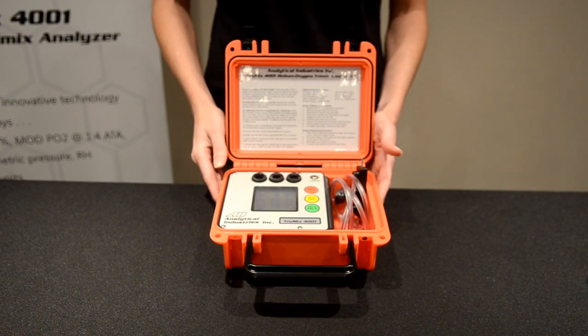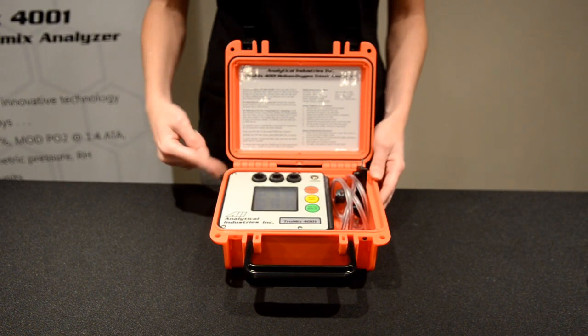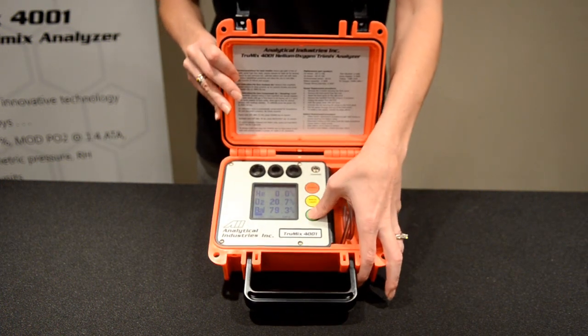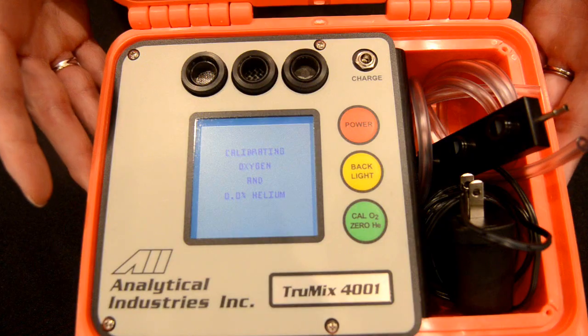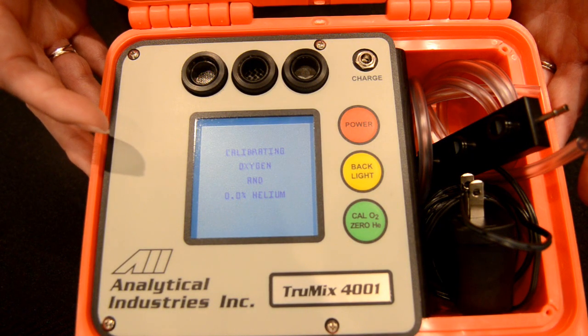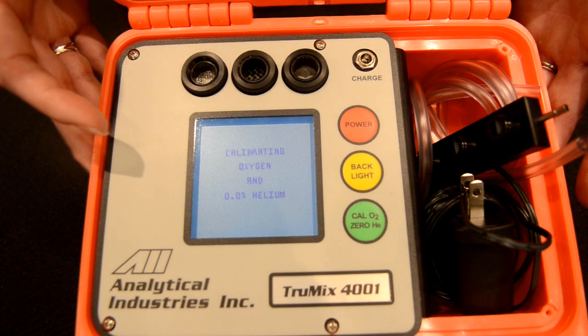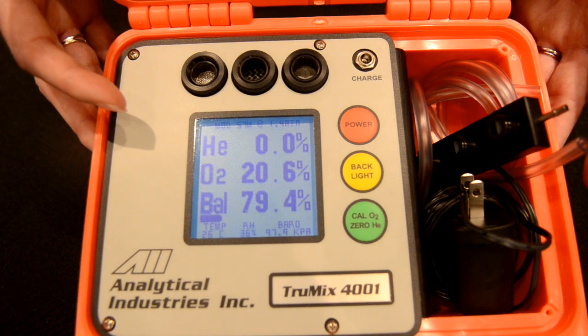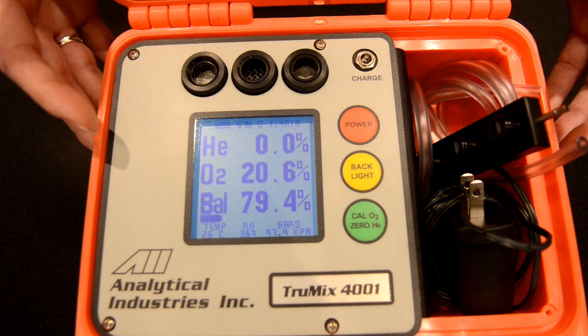Calibration of the TruMix analyzer is very simple. We expose our sensors to the surrounding atmosphere and press the green calibration button. This calibrates the oxygen sensor at atmospheric concentration and zeros the helium sensor at the same time. Once the unit has successfully passed calibration, that will be displayed, and you're ready to start sampling.